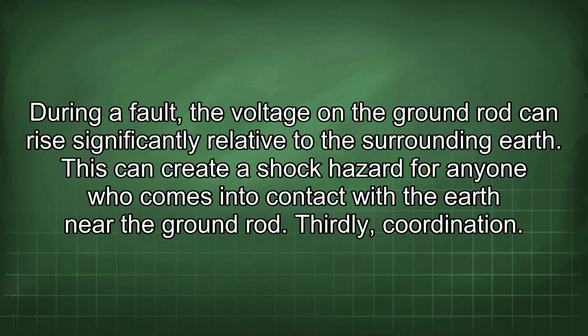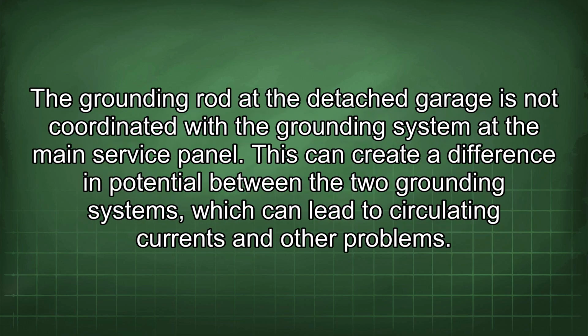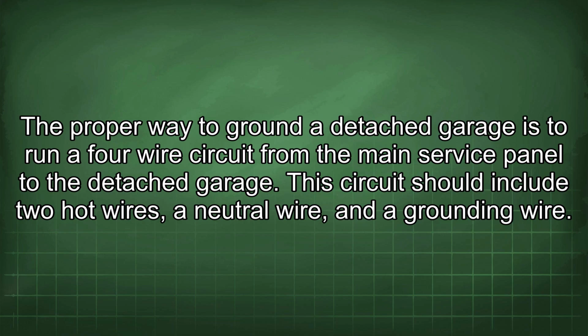Thirdly, coordination. The grounding rod at the detached garage is not coordinated with the grounding system at the main service panel. This can create a difference in potential between the two grounding systems, which can lead to circulating currents and other problems. The proper way to ground a detached garage is to run a 4-wire circuit from the main service panel to the detached garage.